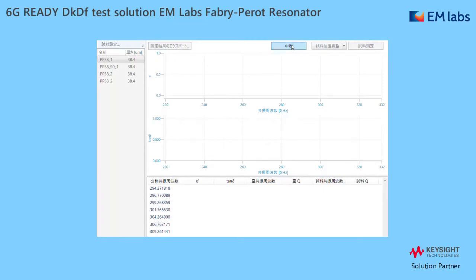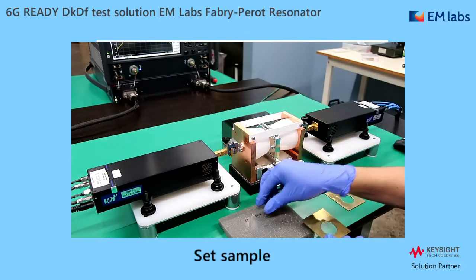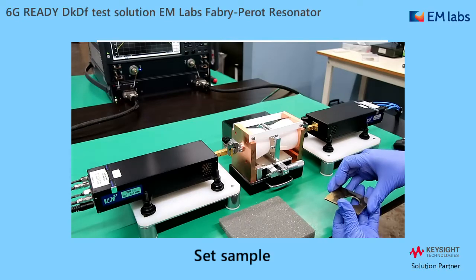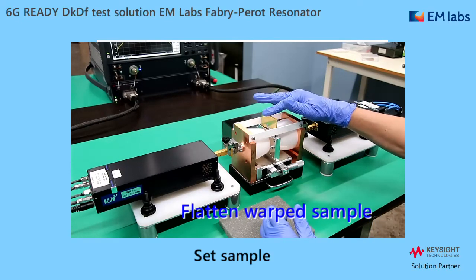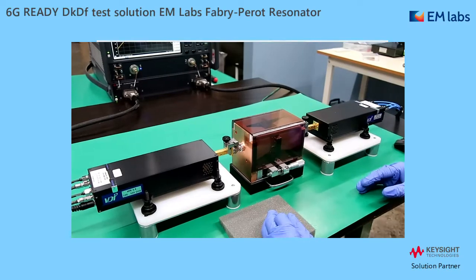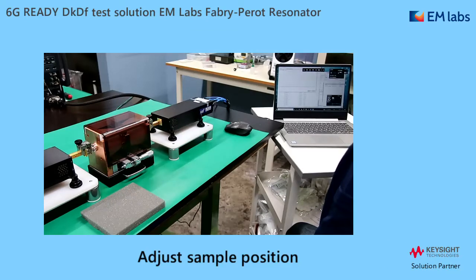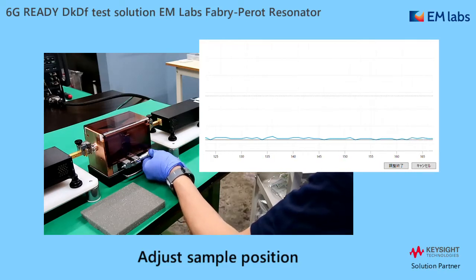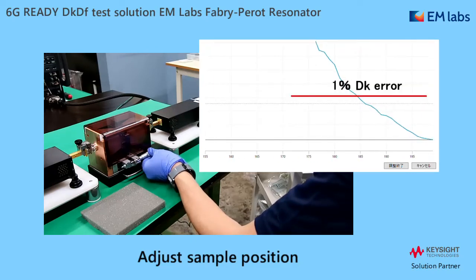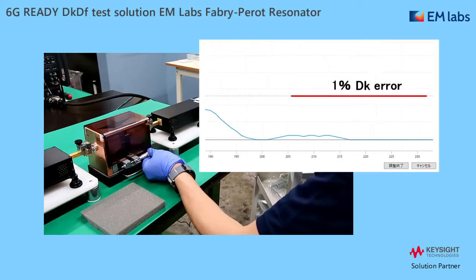Now I set the sample to the fixture. Remove the sample plates and sandwich the sample. With this method, even a very thin film can be set easily. Another advantage is that you can make a warped sample flat. Finally, set the cover for stable measurements. Then click 'adjust sample' to start adjustment to position the sample exactly at the center of the fixture. Slowly rotate the knob until the trace comes to the bottom. You can see the adjustment completed very accurately, as this line shows the 1% error in Dk measurement.